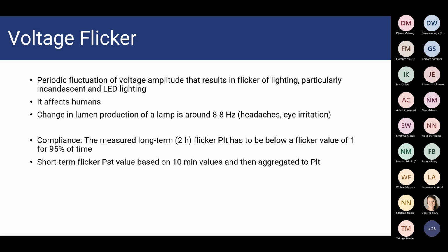We often neglect the impact that something like a voltage flicker or sustained overvoltage can have on plant equipment, but also plant personnel. So if you are aware of a voltage flicker issue that could lead to someone with photosensitive epilepsy having a stroke or a seizure on your watch, that it is absolutely something you could have avoided or investigated in time. If you look at this specific slide, long-term measured flicker over 2 hours, that's not something you will see instantaneously, but an employee sitting at a desk for sustained periods of time exposed to this kind of flicker really has negative health impacts as well.